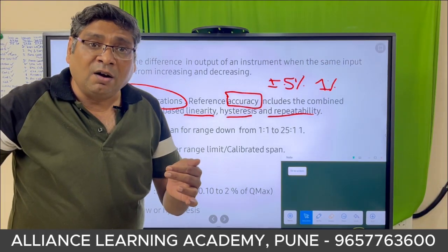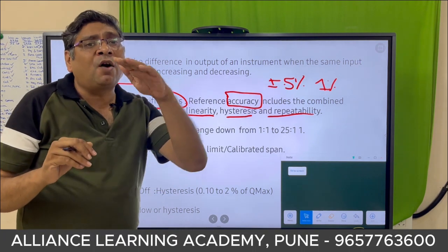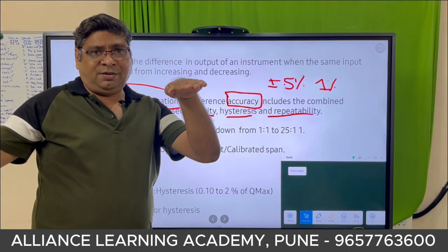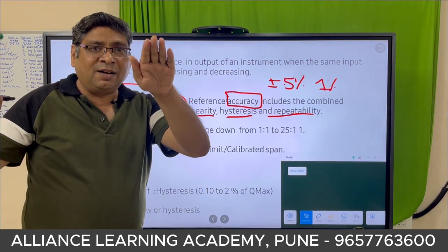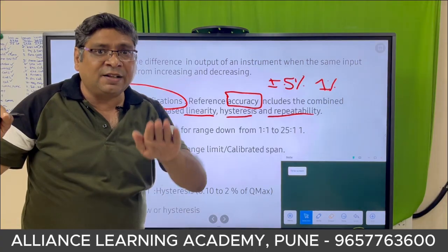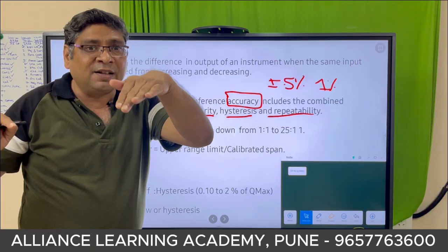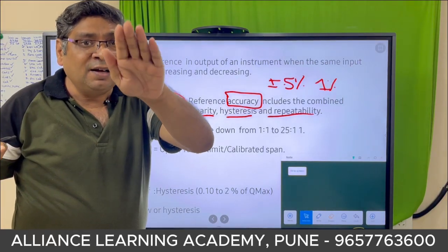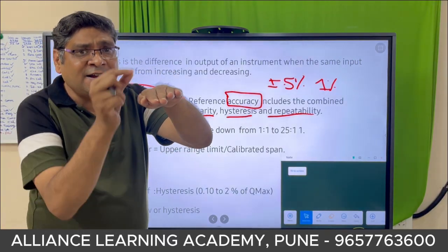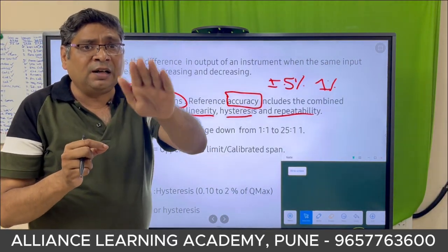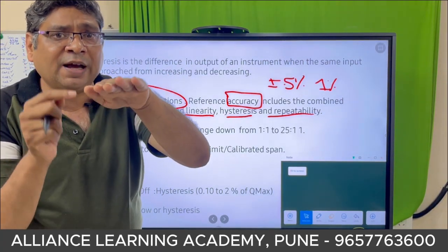be chattering. Oh, you don't understand? Again I will tell you, okay. Now you see the example of a level, and you have a level switch, right? Now the level should not chatter. If it goes like this and this, then only my switching action will happen. But if it is like this and this, then there should not be any on and off action. So we will put a hysteresis range, and within that range of the waves of this level or change of the level, there should not be any switching effect.